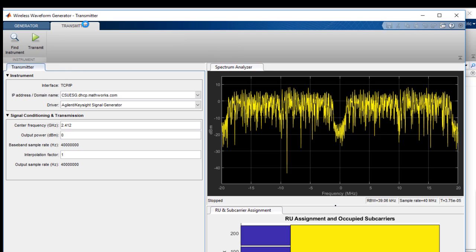The app will automatically search for instruments that are connected to the local network. We choose our instrument, and then all we need to do is set the center frequency and the output power of the signal.